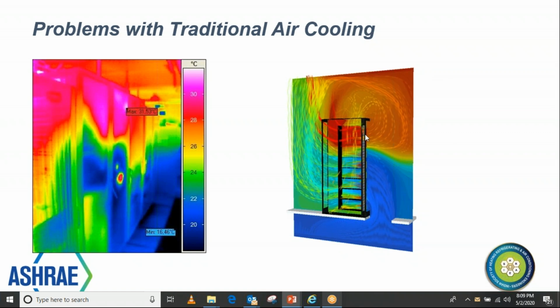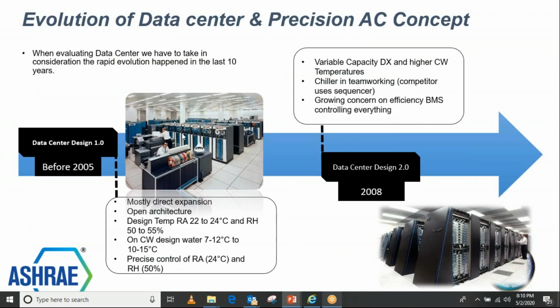So we must ensure that up to the top of the rack, we are able to have a uniform airflow pattern. For that, we may have to put blanking plates in the rack or in the switch rack, avoid the cold air loss there, have the proper airflow pattern, and ensure that sufficient air is coming in front of the rack with the right amount of CFM. There should be proper static pressure maintained under the floor, or sensors in front of the racks to take measurements, and then allow these sensors to let the cooling unit fans increase or decrease the fan speed. So this is very important to have.